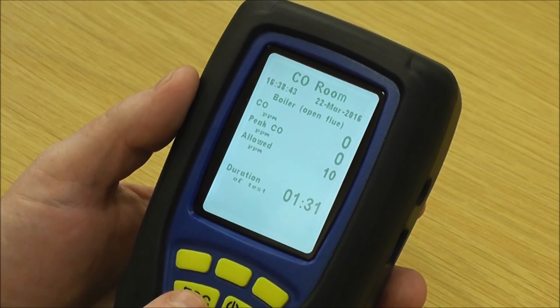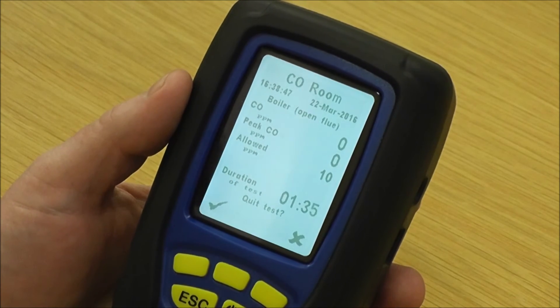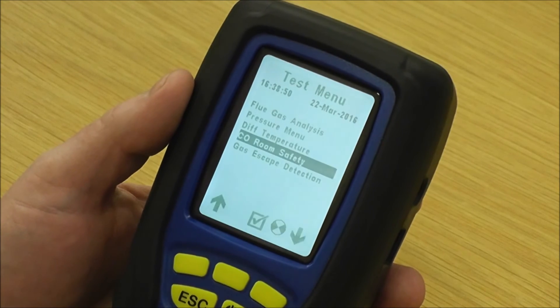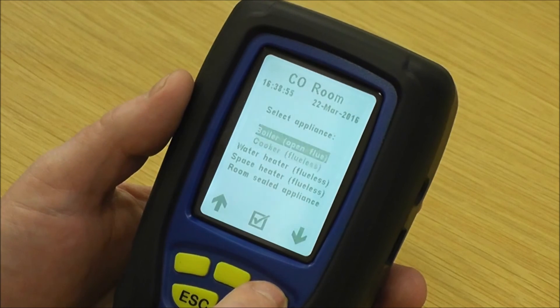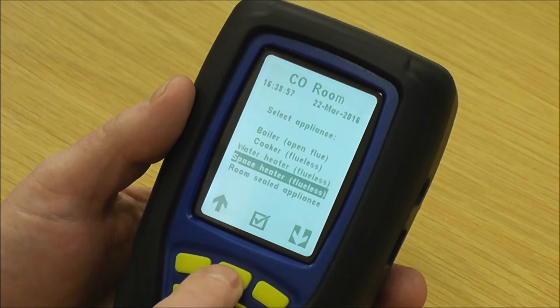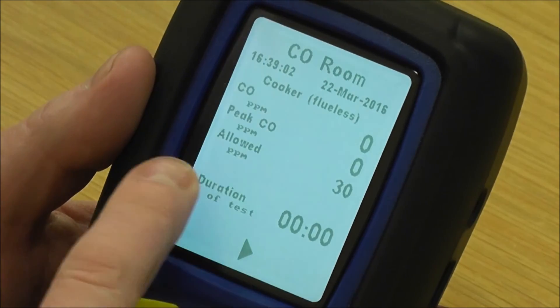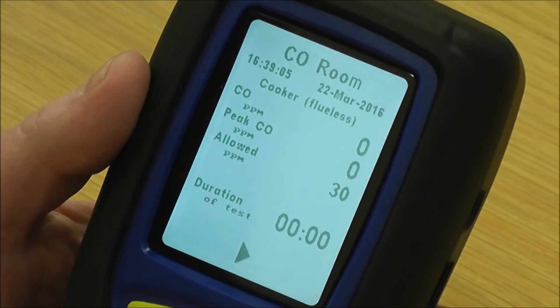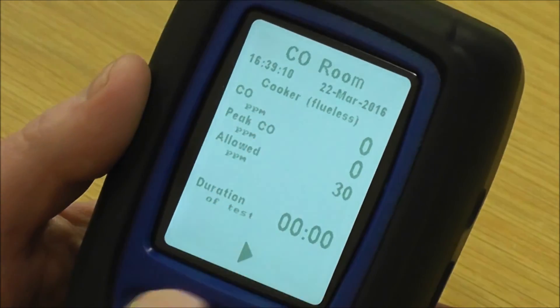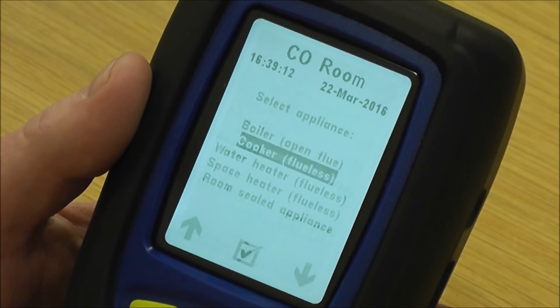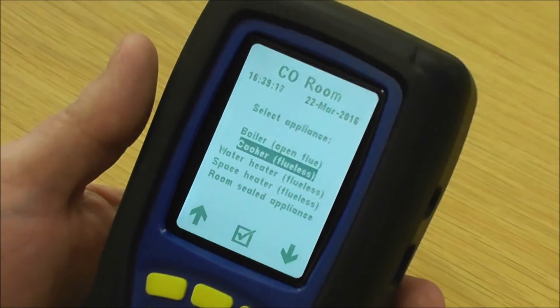I'm just going to press escape to come out of that. It does ask, are you sure you want to quit the test, because you could be many minutes through and you don't want to waste that time. If I go back to room safety and pick another one — for example, if I pick cooker — the allowance changes. You see that's 30 ppm over the set duration. When you do the printout it titles it to whatever appliance you've picked. Nice and easy — the analyser does the job and at the end tells you whether it's passed or failed.